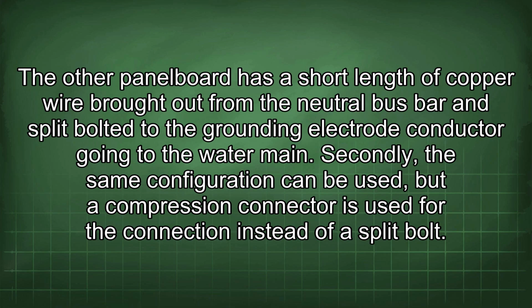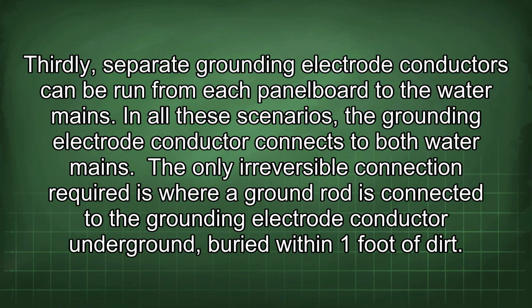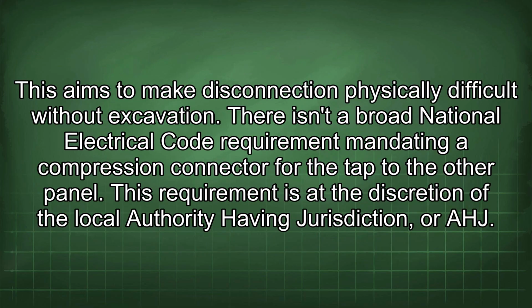Secondly, the same configuration can be used, but a compression connector is used for the connection instead of a split bolt. Thirdly, separate grounding electrode conductors can be run from each panelboard to the water mains. In all these scenarios, the grounding electrode conductor connects to both water mains. The only irreversible connection required is where a ground rod is connected to the grounding electrode conductor underground, buried within 1 foot of dirt. This aims to make disconnection physically difficult without excavation.